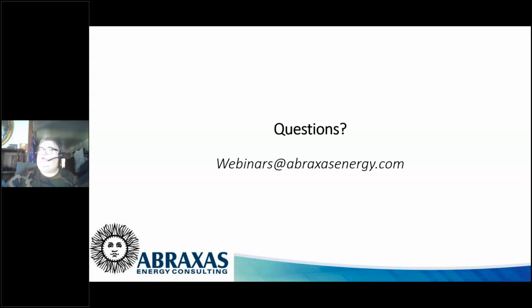Well, there you get into, and then probably another idea for a webinar, chiller efficiencies at part load. Then you start talking about how your kW per ton falls out. In this case, these chillers had 2 compressors on them at variable speed on both of them. So if I can get close to 50%, I go to 1 compressor running high versus 2 compressors running very low. But you need to look at your chiller efficiencies at part load to find their sweet spot. Again, back in the old days, we thought 100% was best. No, we found out that 60, 80% is better.